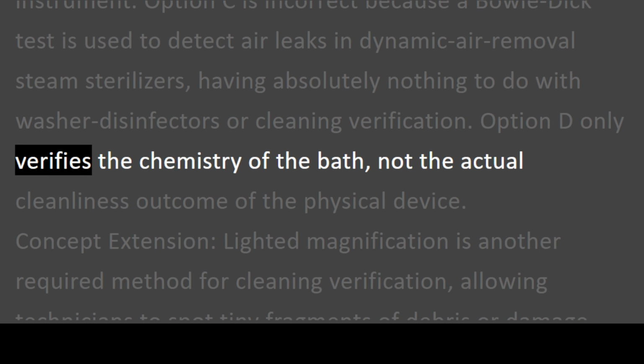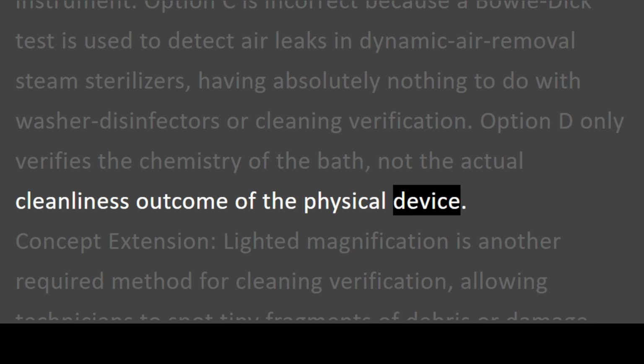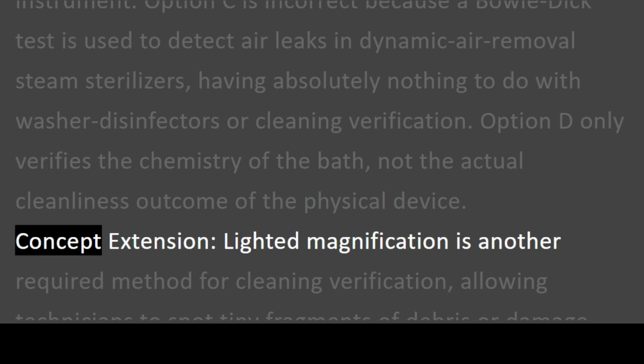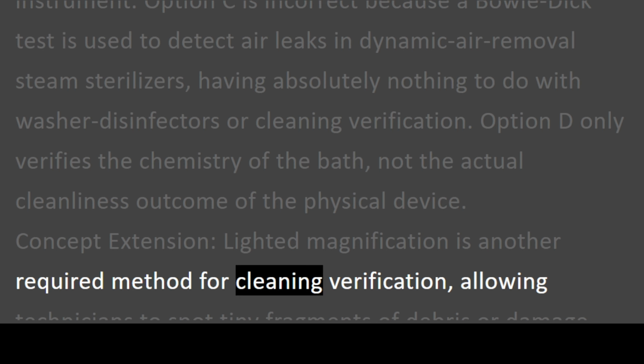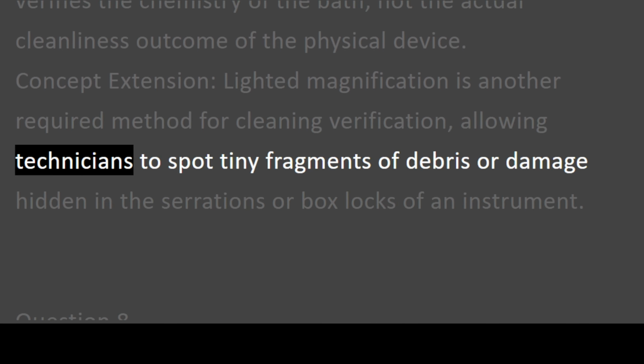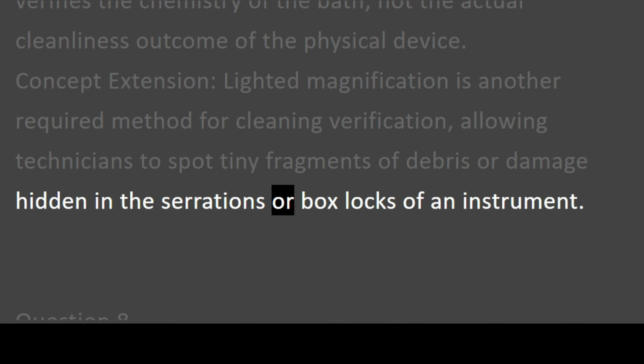Option D only verifies the chemistry of the bath, not the actual cleanliness outcome of the physical device. Concept extension. Lighted magnification is another required method for cleaning verification, allowing technicians to spot tiny fragments of debris or damage hidden in the serrations or box locks of an instrument.